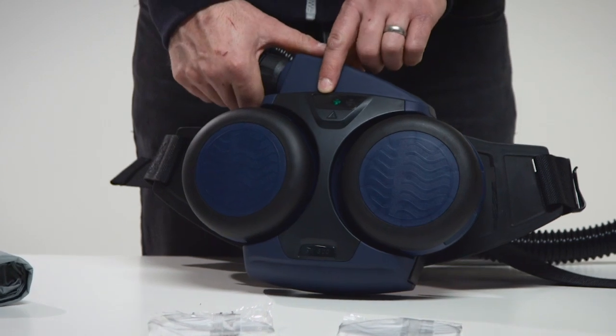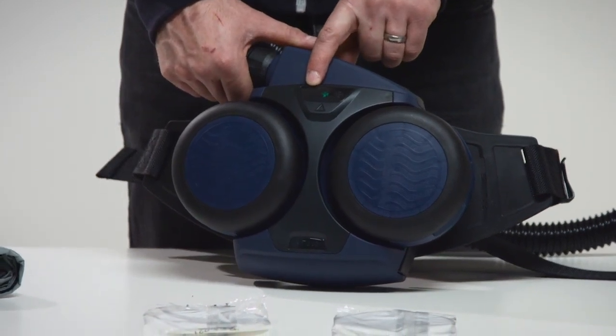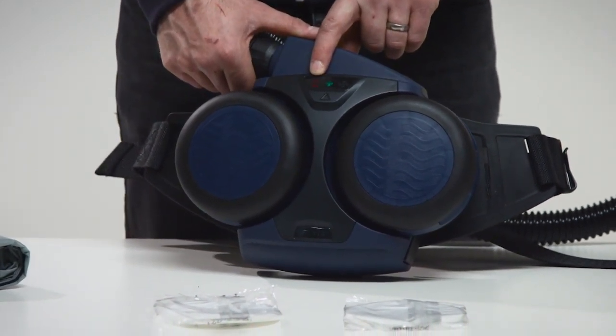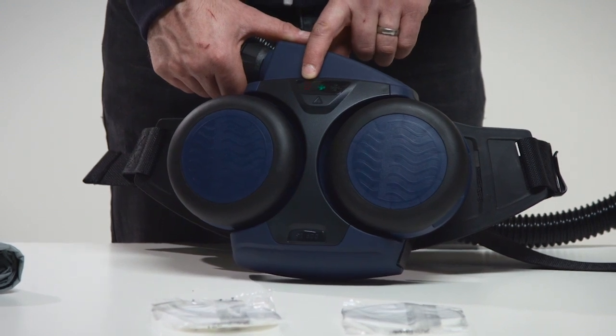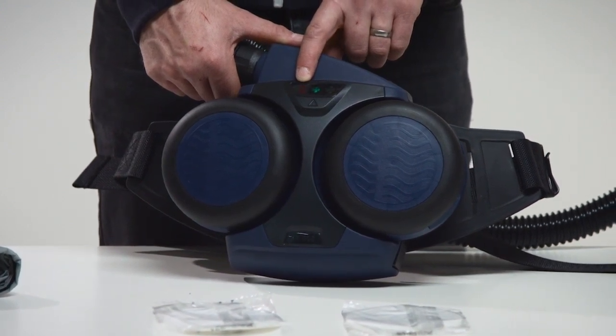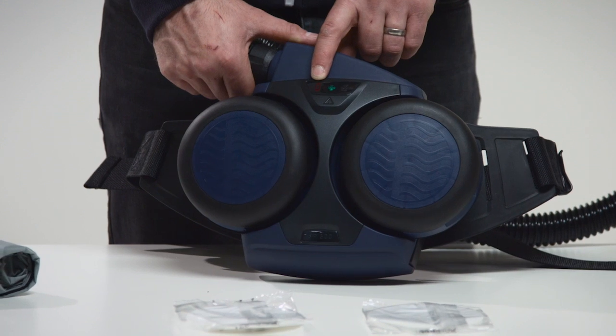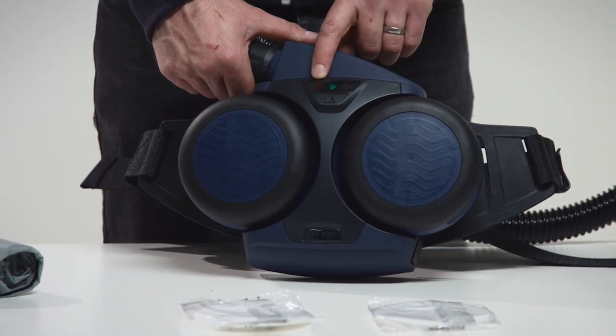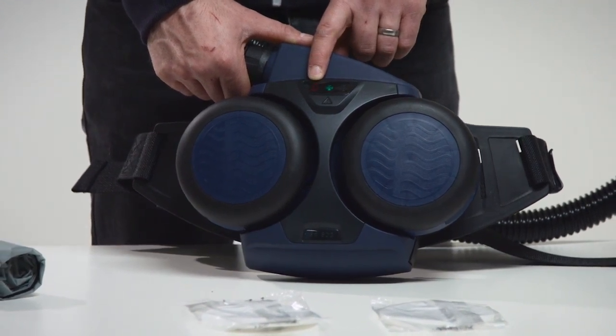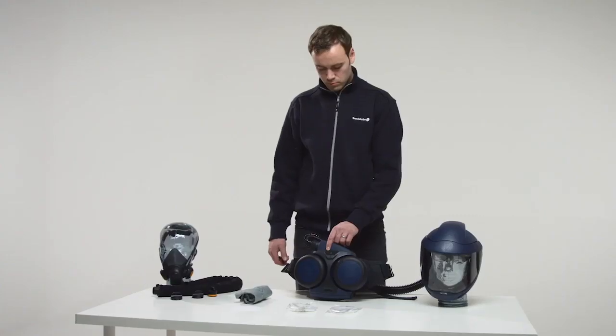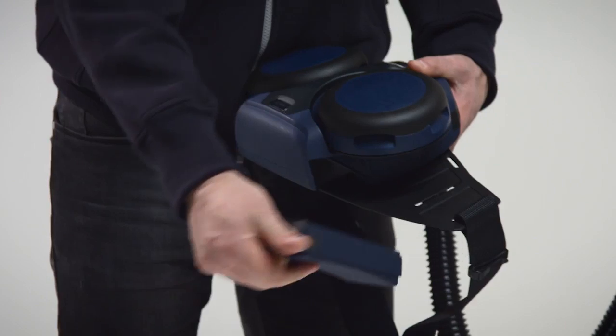If the battery capacity is lower than 5%, a sound signal will be repeated twice at intervals of 2 seconds. The built-in vibrator will be activated twice at intervals of 2 seconds. The battery symbol of the display will flash red. Action: Immediately interrupt the work, leave the area and change or charge the battery.